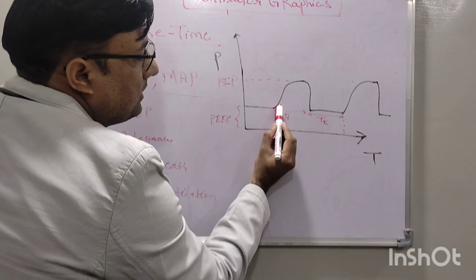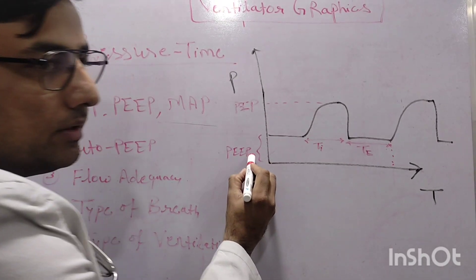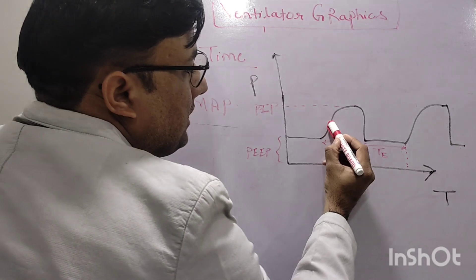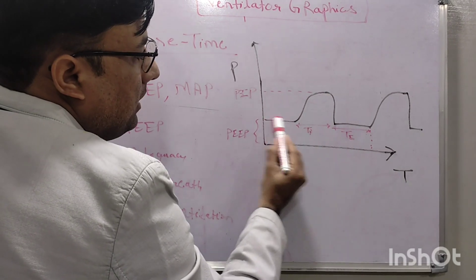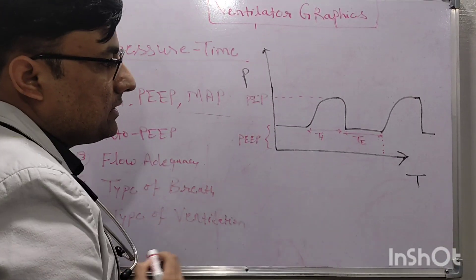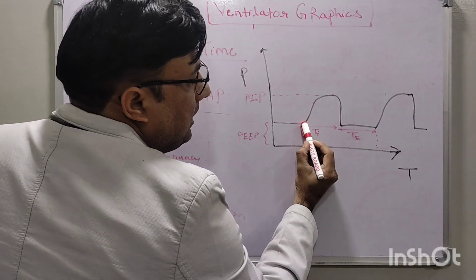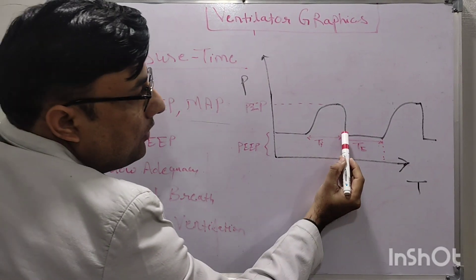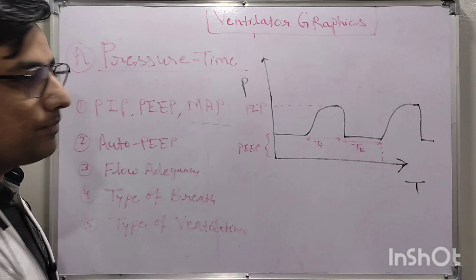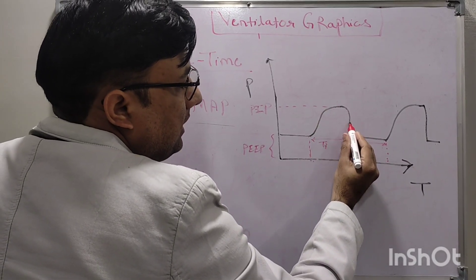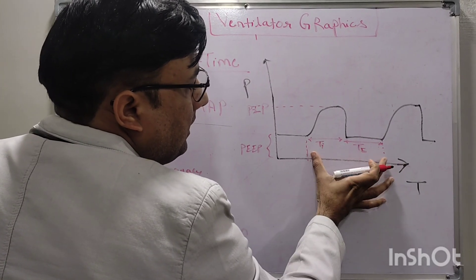In the pressure-time curve, the x-axis is time and the y-axis is pressure. The inspiration is not starting from zero; it starts from PEEP. The inspiratory pressure increases and reaches the PIP — that maximum pressure during the respiratory cycle is the PIP, and the baseline is the PEEP. The inspiratory time goes from the start to the end of inspiration. The expiratory time goes from the start to the end of expiration. The complete cycle — Ti plus Te — is one respiratory cycle.